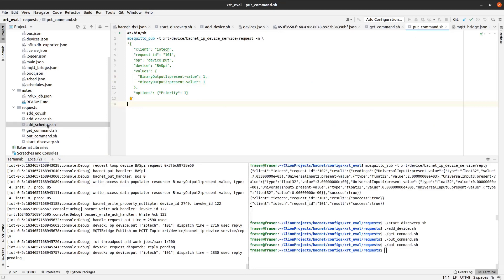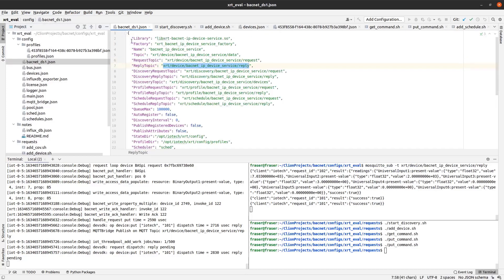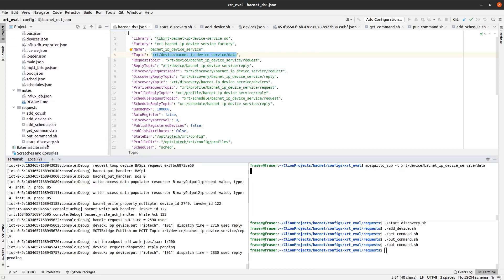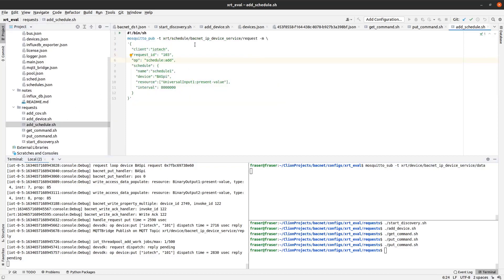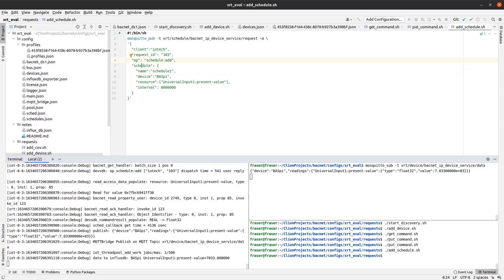The next thing that I will do is to set up a schedule so that the BACnet device service will automatically read specific BACnet values at periodic intervals, in this case every 8 seconds. You can see the JSON payload for the schedule request message on the screen. In the first console, I will start an MQTT client which will subscribe to XRT's BACnet data topic. In the second console, I will issue an MQTT request to add the schedule. You can see in the first console that data values for Universal Input 1 are automatically read every 8 seconds.